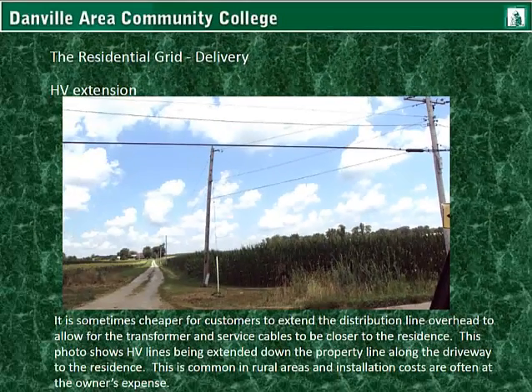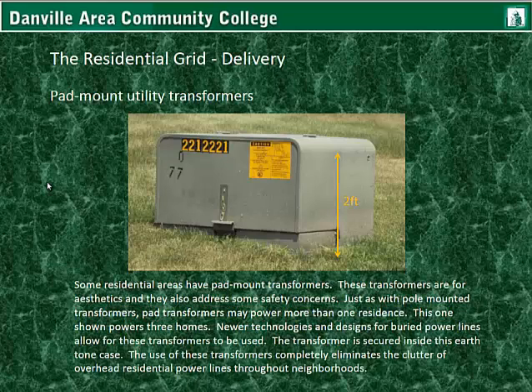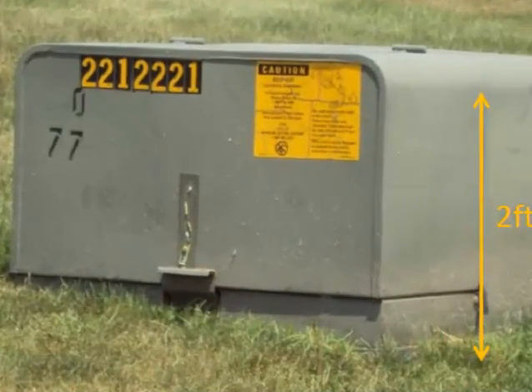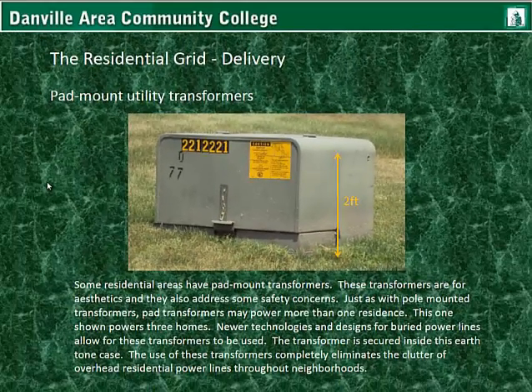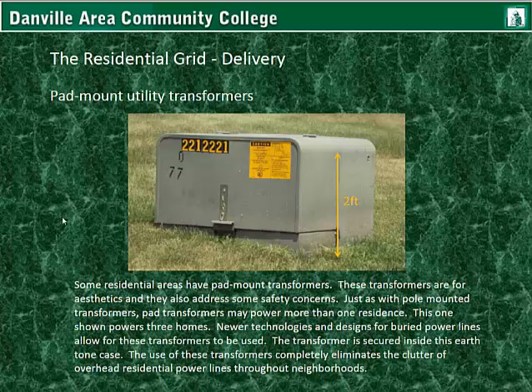Also, with this far of a run, you would get voltage losses if you tried to run a lower voltage cable all the way down to the home, so a transformer being located here wouldn't be an option. Pad mount utility transformers — some residential areas have pad mount transformers. These transformers are for aesthetics and they also address some safety concerns. Just as with pole mounted transformers, pad transformers may power more than one residence. This one shown powers three homes. Newer technologies allow for these transformers to be used with buried high voltage lines. The transformer is secured inside an earth tone case, completely eliminating the clutter of overhead residential power lines throughout neighborhoods.